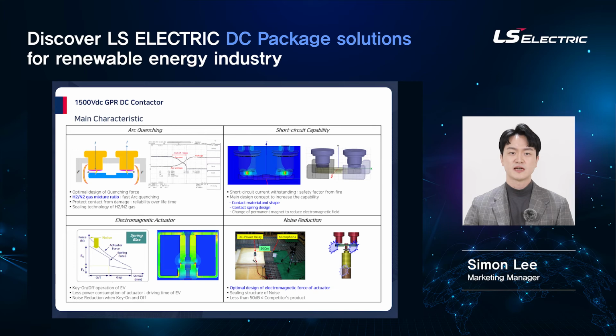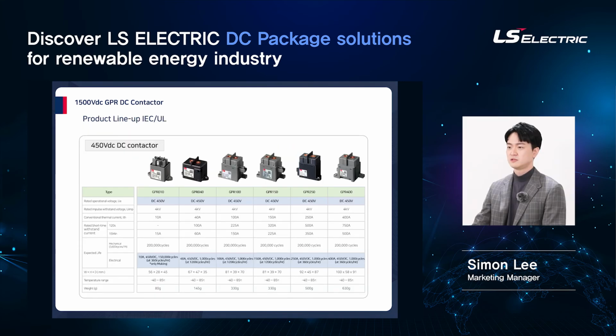On demands of designing the contactor for high capacity, there are four major design features we deal with: arc quenching, short circuit capability, solenoid actuator designing, and noise reduction. Based on these considerations, we are able to mass produce our DC contactor lineup with technical confidence. Please kindly refer to the lineup of our DC contactor from 450 volts to 1000 volts, which are certified by CE, CCC, CB, and even UL.